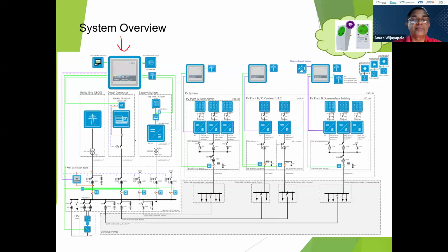They are connected through their transformers — in case of the grid, because we are getting 11 kV. The diesel generator is directly connected because it is generating at 400 volt three-phase. The battery is connected through the inverter, and the transformer connects the inverter to the grid. So all are generating at 400 volt three-phase and connected to the bus here, which is extended to the loads as well as to the generation in the three buildings we talked about.